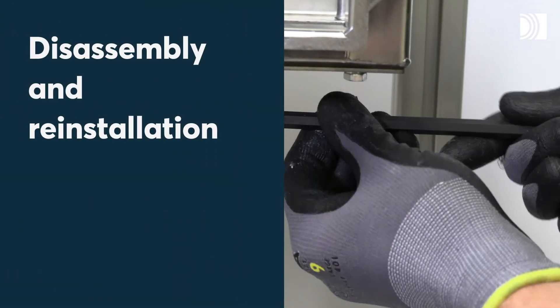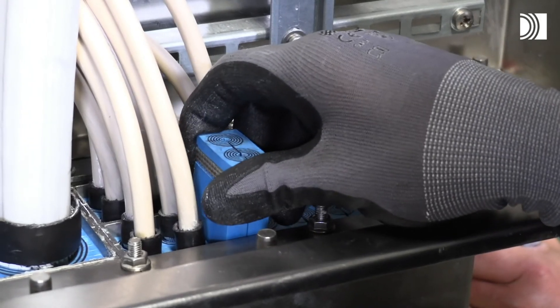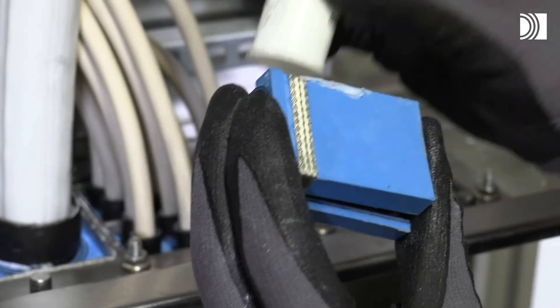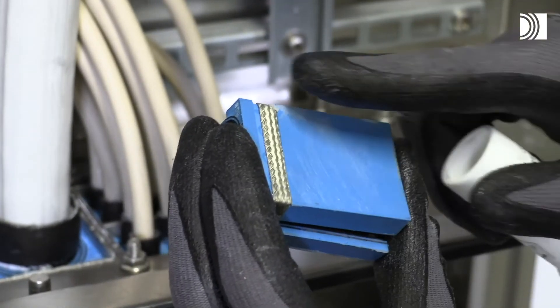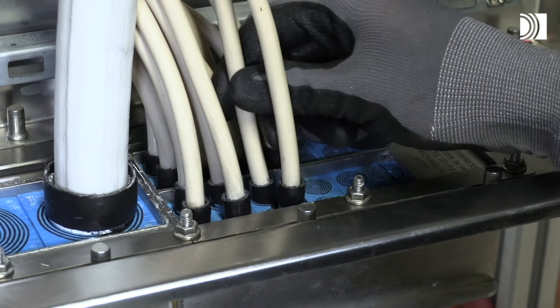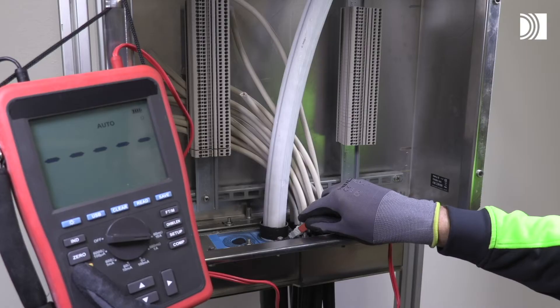Disassembly and reinstallation. It's easy to add a new cable. Release the compression. Push out a spare module and adapt it. Lubricate the inside surfaces of the frame and the module. Insert the module halves and the cable. Tighten the compression unit and verify earth continuity.